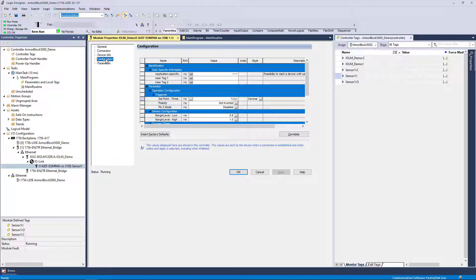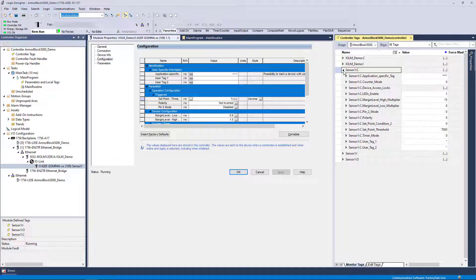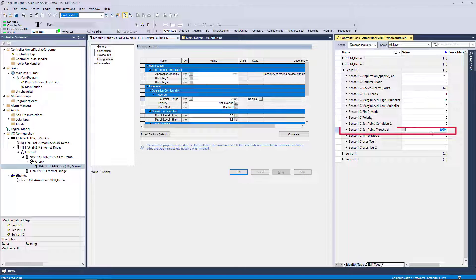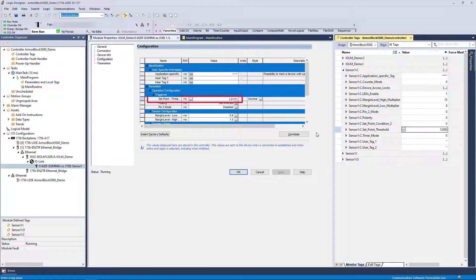For devices in ADC mode, configuration changes can also be made via device tags. Let's change the value to 12000 in the configuration tag for this IO-Link device. Observe that the value is updated in the configuration tab, but it is important to understand that this change has not made it to the IO-Link device yet.